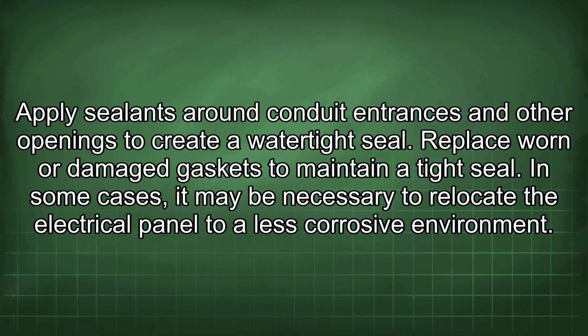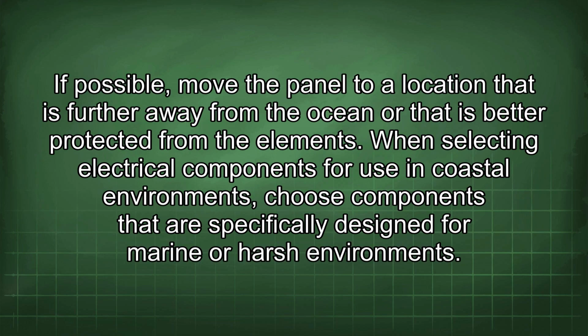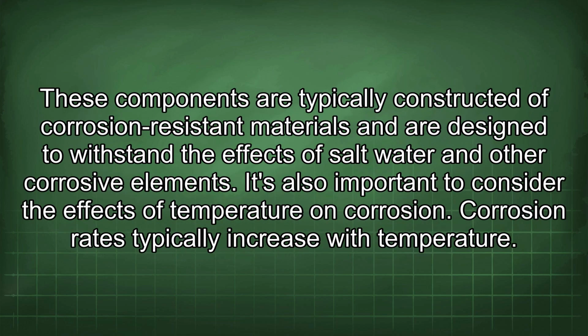In some cases, it may be necessary to relocate the electrical panel to a less corrosive environment. If possible, move the panel to a location that is further away from the ocean or that is better protected from the elements. When selecting electrical components for use in coastal environments, choose components that are specifically designed for marine or harsh environments. These components are typically constructed of corrosion-resistant materials and are designed to withstand the effects of salt water and other corrosive elements.